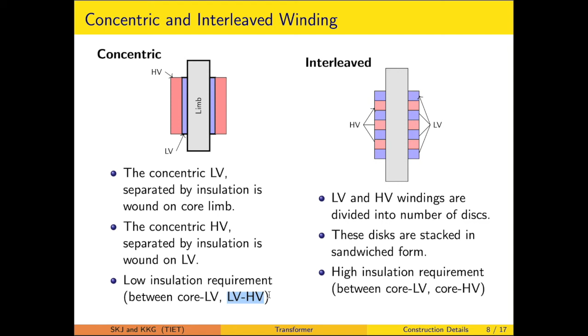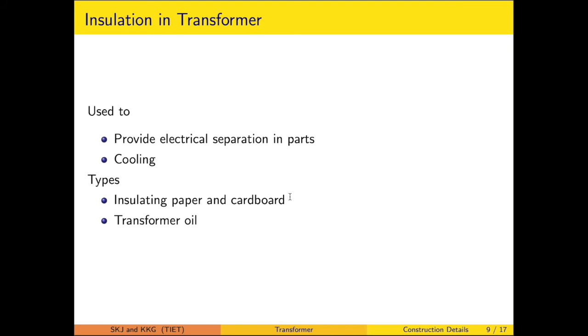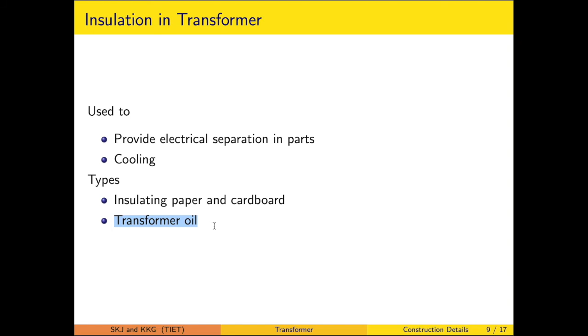There are different types of insulations which are used in transformers. We are seeing this in the smaller or modular size of transformer, while others are specifically for the power transformer. The intention of the insulation is first to provide electrical separation, and another purpose is cooling. Electrical separation is needed for all types of transformer, whether of small rating or so; we have seen that the core laminations are separated by insulating materials. However, cooling is used specifically for the large power transformer. The materials used are insulating paper, cardboard and transformer oil. Transformer oil has a specific purpose of providing cooling in addition to the insulation.